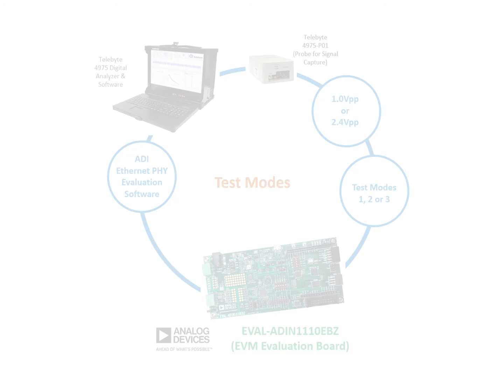Hello, today we're going to use the Analog Devices ADIN1110 EBZ evaluation board to do some IEEE 802.3 CG compliance testing. The first thing we want to do is put the Analog Devices evaluation board into the test mode 1 signal. So I have my notes here on how to do that. Using the 1110, we use a PHY write command. So PHY writes and reads to certain registers that are in a hex value with certain values. So I have a program here that's using Termite, and I'm connected to COM13 here at 115,200 bits per second, 8 bits, no parity, and no handshaking.